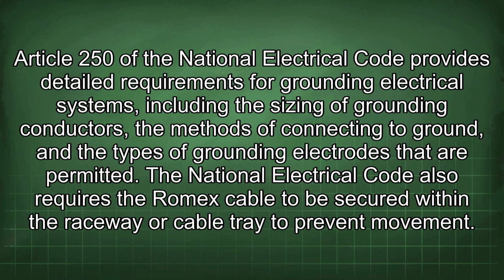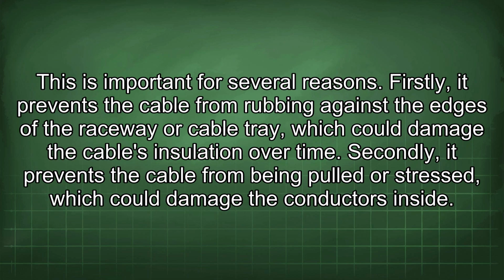Article 250 of the National Electrical Code provides detailed requirements for grounding electrical systems, including the sizing of grounding conductors, the methods of connecting to ground, and the types of grounding electrodes that are permitted. The National Electrical Code also requires the Romex cable to be secured within the raceway or cable tray to prevent movement. This is important for several reasons. Firstly, it prevents the cable from rubbing against the edges of the raceway or cable tray, which could damage the cable's insulation over time. Secondly, it prevents the cable from being pulled or stressed, which could damage the conductors inside.